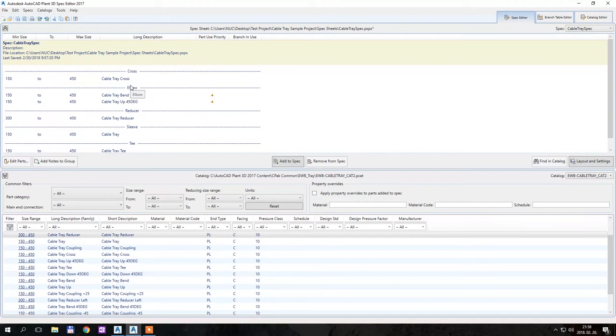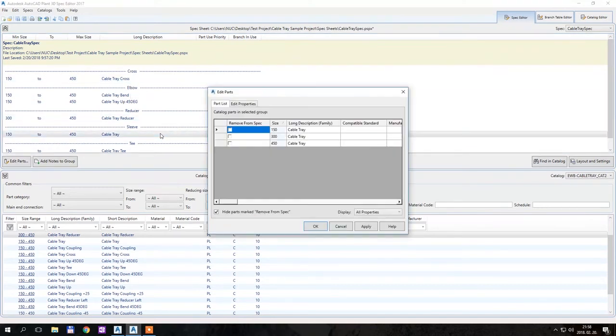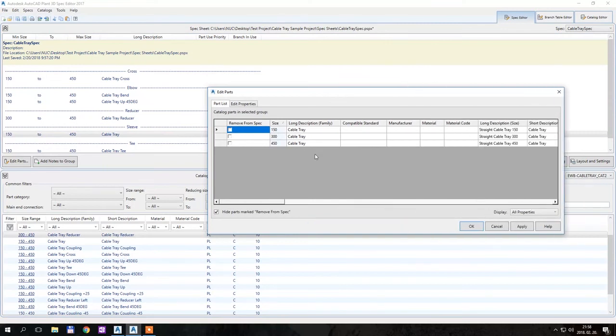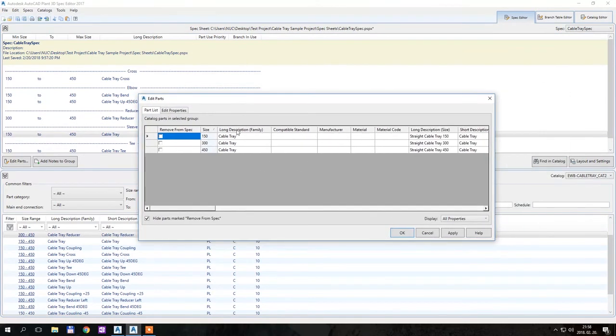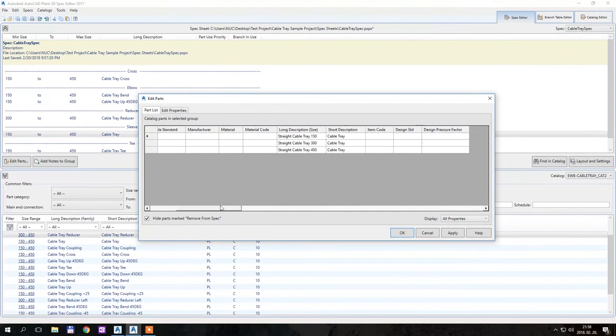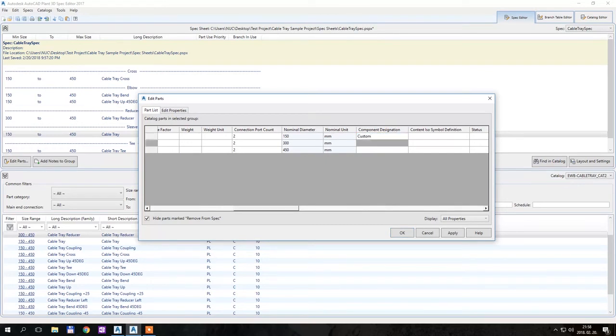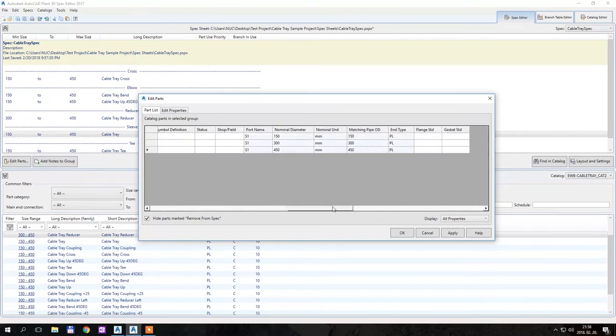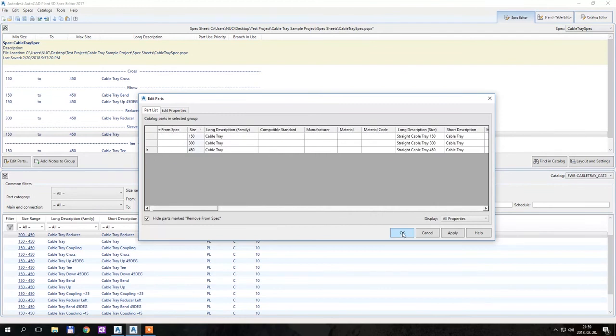You shouldn't forget that if you want to change the length of the straight cable tray elements, you have to enter in the component designation the value 'Custom'; otherwise you cannot edit the length of the straight cable tray elements inside the Plants 3D model. So I enter 'Custom' here — I just copy-pasted it — and I hit Save.